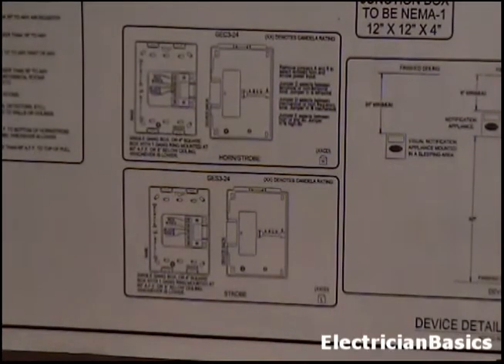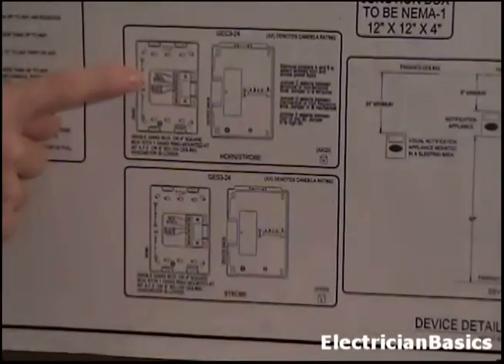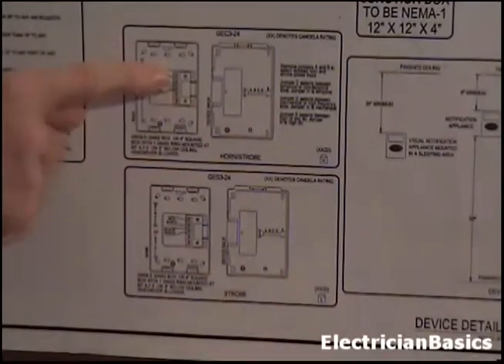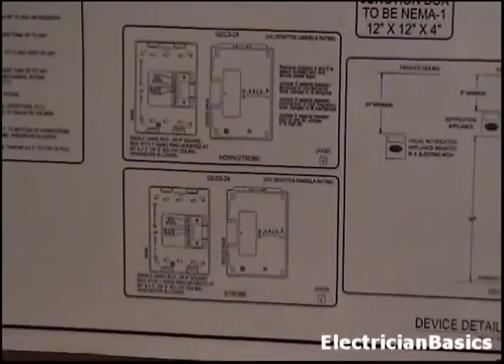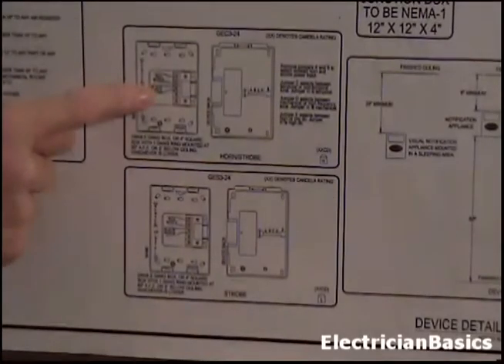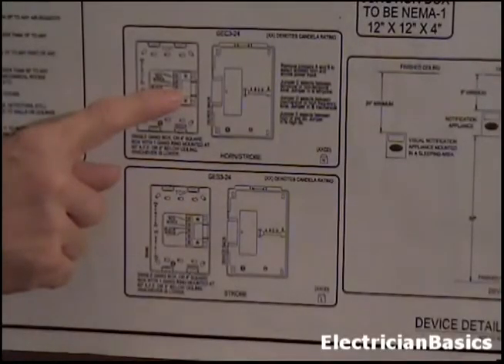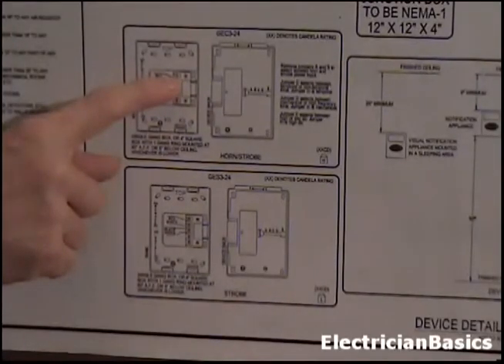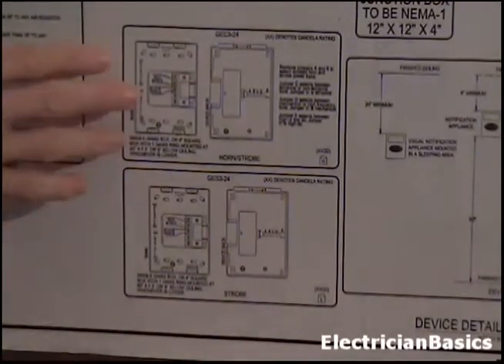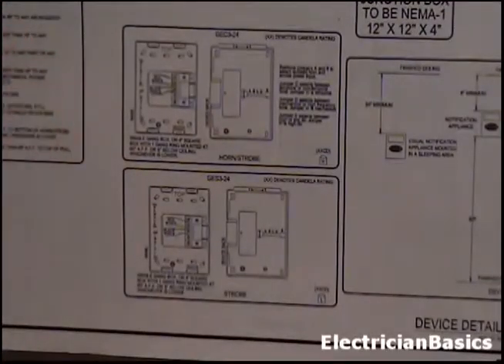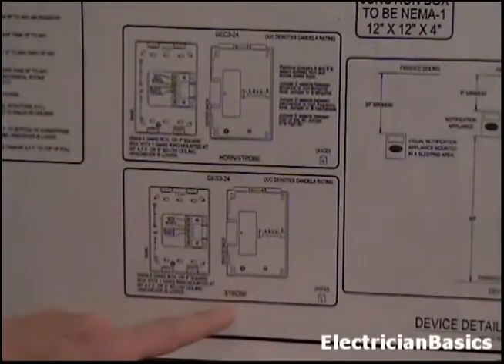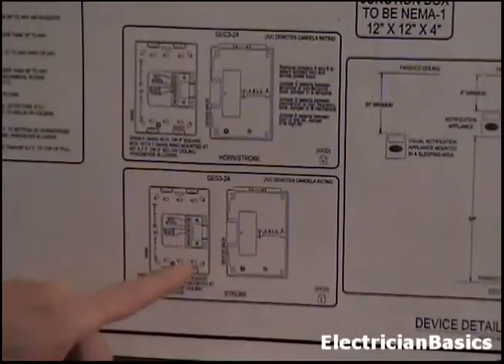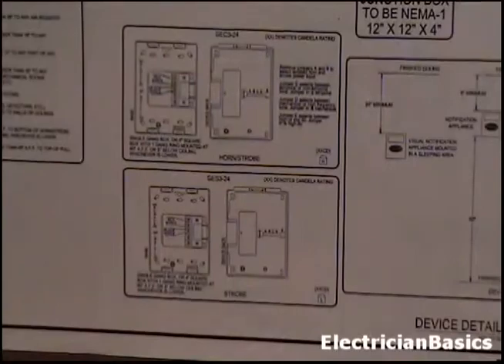Now we're given these things on how we have to do this. Now this says the red wires, once you look at it, there's going to be these 6 terminals you can land them. You're going to have 2 sets of cable, each with a red and a black wire going into this. And you can see both black wires are going to go to the 3rd one from the top, and the red wires are going to go to the 1st and the 2nd one. So this gives you the detail on how to wire it for this system. Now on the strobe, if we look at it, it's pretty much the same on the wiring. And that's nice because we won't end up getting those two confused if they're different. If they were slightly different, there could be a problem with that.